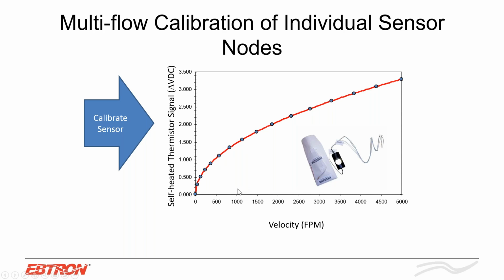Now we also calibrate these units to NIST traceable standards. NIST stands for the National Institute of Standards and Technology. And basically we send our unit off to NIST. We get a reported calibration based on their laser Doppler anemometer. We take that reported calibration and we transfer it to our production wind tunnels at the factory. So each one of these sensor nodes is calibrated to 16-point NIST traceable standards.